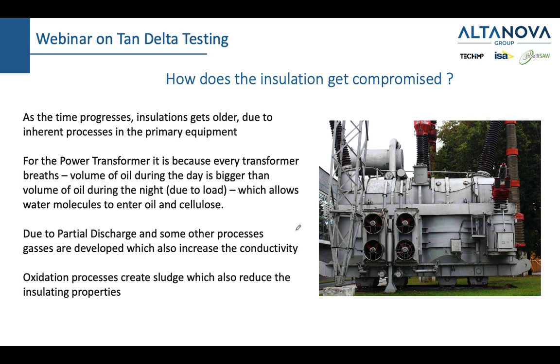And inside the transformer, the oil increases its volume. And as the oil increases its volume, it's simply bigger. But then the night comes, the temperature drops, people go to sleep, and the transformer is not used at 80% anymore, but maybe 20 or 30% of its nominal power. And since the temperature reduces, the oil reduces its volume. Then again, the morning comes, the oil increases the volume, the night comes, it decreases the volume. So I hope you follow me and you understand that this is a definition of breathing. The same thing when you breathe. If you want to breathe in, you will expand your lungs, your chest, in order to suck the air inside. And then you will contract it to push it outside. The same is done with the transformer. And that's why the transformer has a breather. The breather is that pipe through which the transformer breathes.